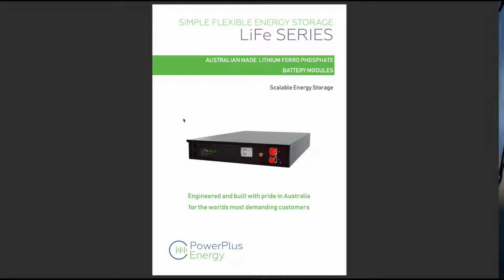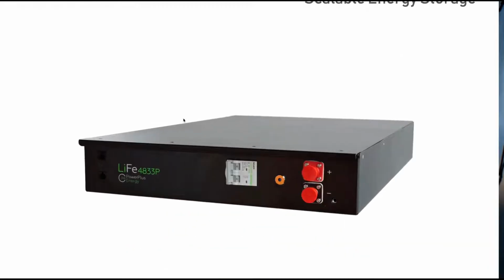So that circuit breaker is a string overcurrent protection device. It is readily accessible. It's on the outside. It can be locked in the off position, and it's marked on and off. So it actually meets all the requirements of 5139 as an isolation device. I'll just zoom in a bit so you can see it there. Yeah, apologies to Power Plus Energy for not showing their later models, but anyway, it's got the same functionality in this unit here.